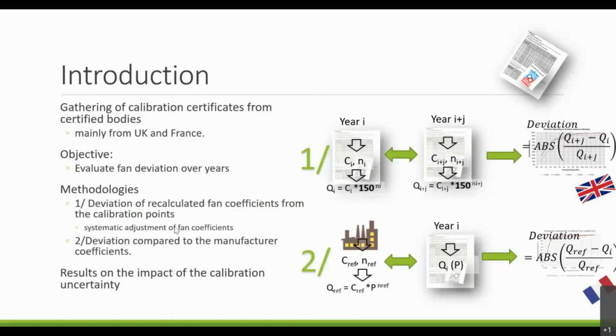In the first part of the study, what we have done is a systematic adjustment of fan coefficients, which means that we have recalculated the C and the N coefficients of each configuration for each fan, for each calibration, and then calculated the flow rate. We have done it at year i, and then the same thing at year i plus j, and we have plotted the deviation between year i and year i plus j.